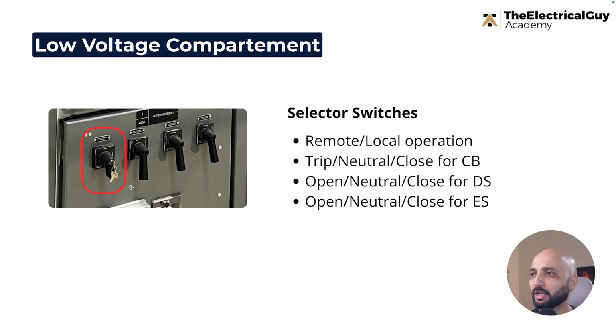We talked about this. You will also see a T-N-C switch for the circuit breaker: trip, neutral, and close. When you put it on the trip side, the breaker will trip. When it's on neutral, the breaker stays in the position it is in. And if you want to close, you put it to the close position and the breaker will close. The same functionality we also have for the disconnector and earthing switch. So those are the selector switches you will commonly find on the low voltage side.